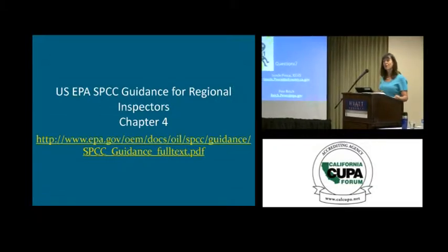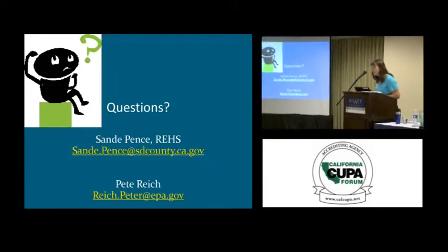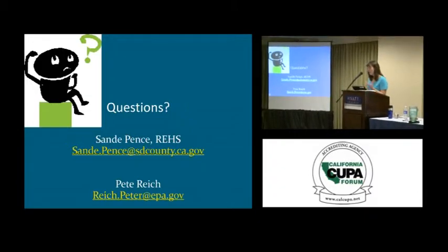Any more questions? Yes, right here. You said transformer oil is exempt under APSA. Does that carry over also to the federal SPCC? The question is, transformer or oil field electrical equipment has exemptions under APSA. Does that apply for federal? And the answer is no. Oil in any type of equipment is subject to the federal rule.